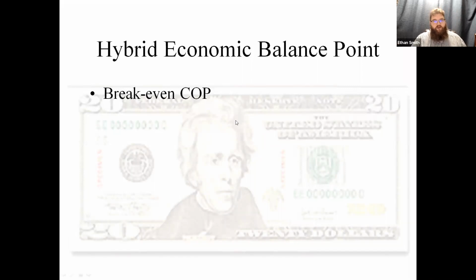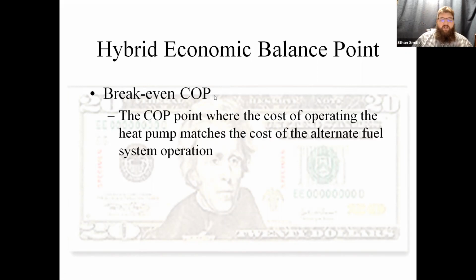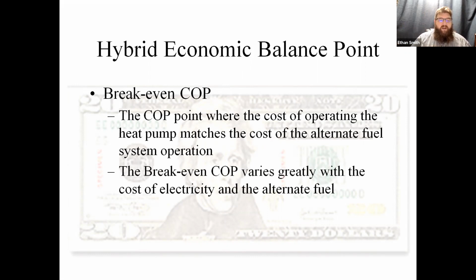We talked about COPs earlier, that coefficient of performance, where we can determine how efficiently our outdoor unit is producing heat at different outdoor temperatures. So the break-even COP is simply the COP point where the cost of operating the heat pump matches the cost of our alternate fuel system. Okay, so it varies greatly. You generally have to recalculate this every year.